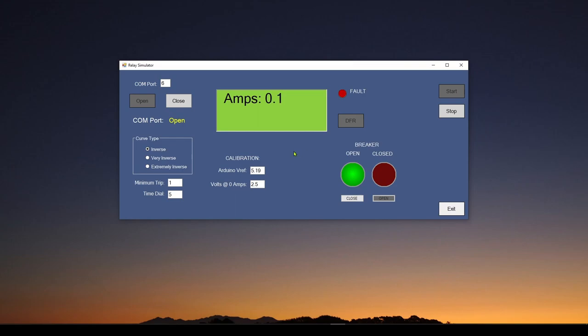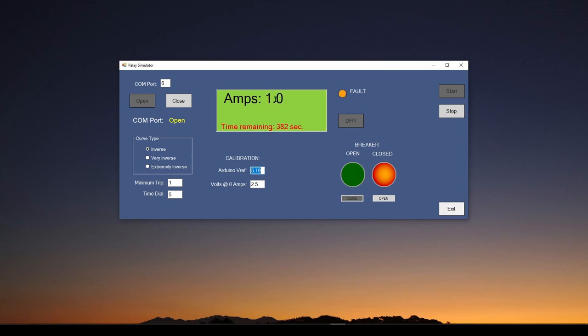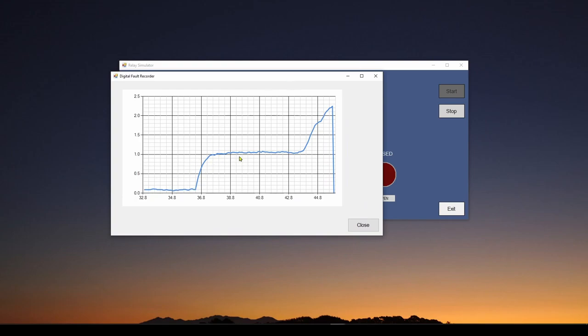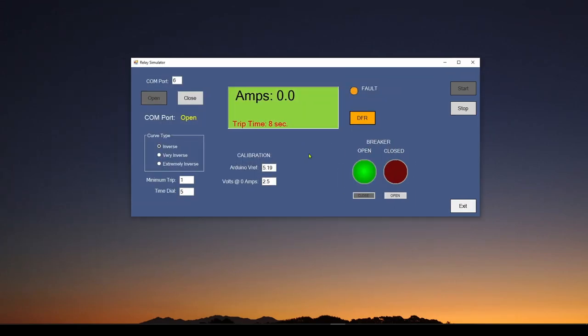Now with the power supply turned on, we can simulate closing the breaker and see what happens. We're going to have one or two amps of current flowing and a minimum trip of one amp. We'll hit close — the breaker closes and we go up to about one amp. Then I cranked the current up and it tripped. It took eight seconds to trip, the current went to zero, and I can hit the DFR to see what happened over time: the current started at about one amp, went up to over two amps, and the relay operated. Now let's take a look at what we added to the application to connect to the DC control relay and do some calibration.